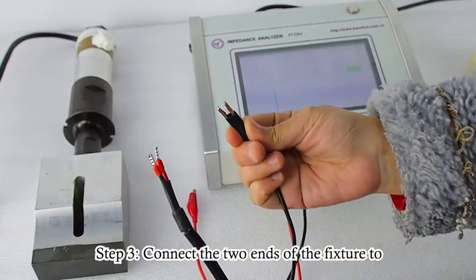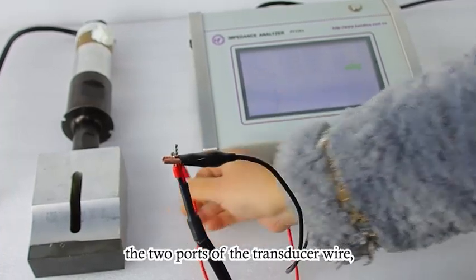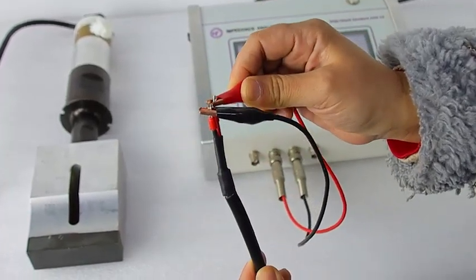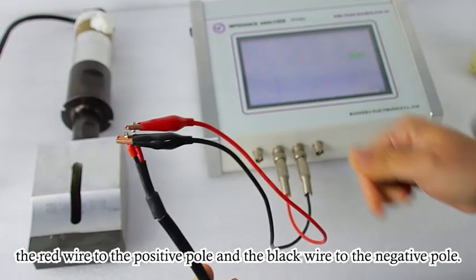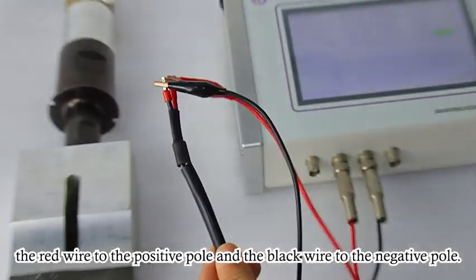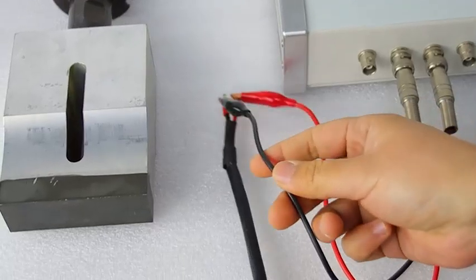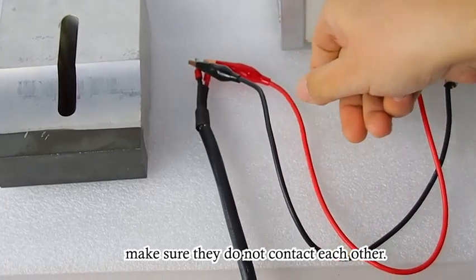Step 3. Connect the two ends of the fixture to the two ports of the transducer wire. The red wire to the positive pole, and the black wire to the negative pole. Make sure they do not contact each other.